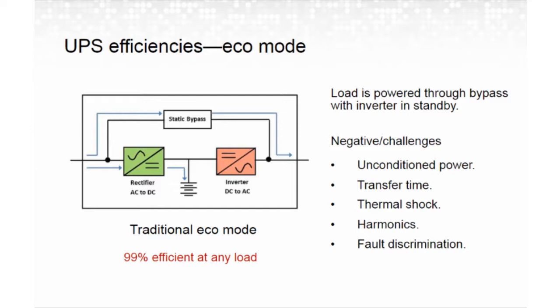Another one is thermal shock. During an event, the UPS is at its critical moment. It's trying to transfer to battery, and now all of a sudden you've introduced another operation where you're transferring the load to inverter from the bypass, and it's going to be done in one big step. That one big step creates a thermal shock to the system, which could cause electronic failures. Another is harmonics. In eco mode, there's no isolation, so all the harmonics from the load are passed right on to the utility or generator.